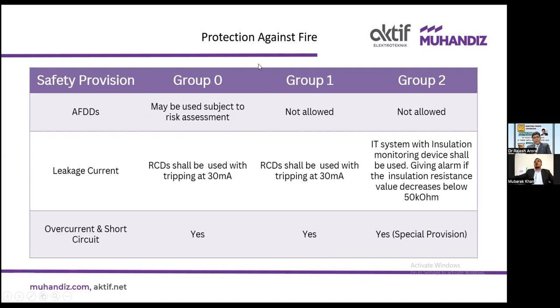Now, coming to protection against fire, one special point mentioned here is that AFDDs are not allowed in group 1 and group 2 locations. In group 0 location, it may be used subject to risk assessment done prior. Second is the leakage current. RCDs shall be used with tripping at 30 milliampere for group 0 and group 1 locations. For group 2 locations, IT systems must be used. In detail, we are going to discuss.